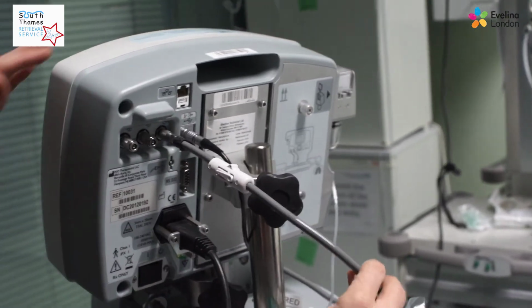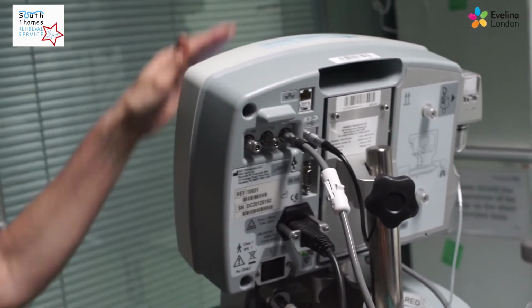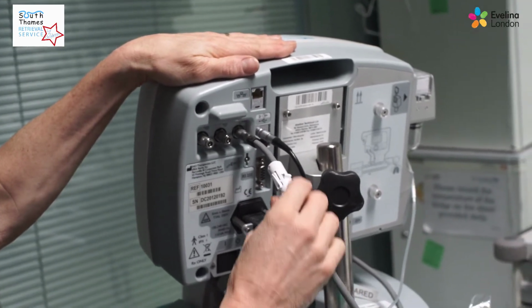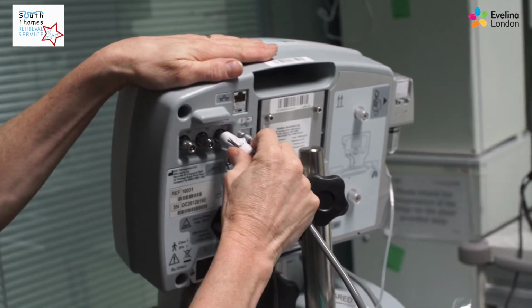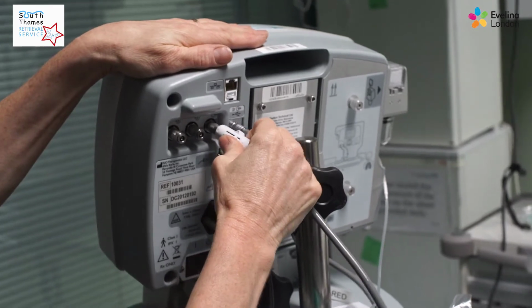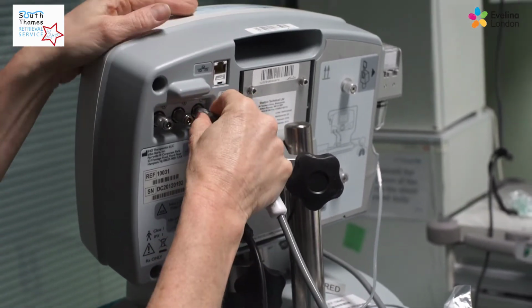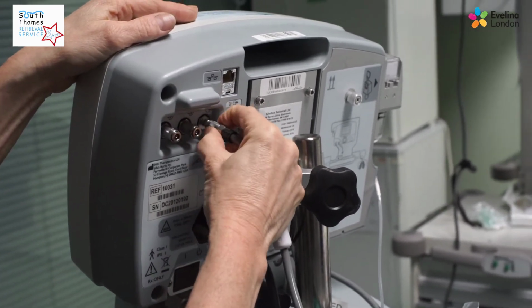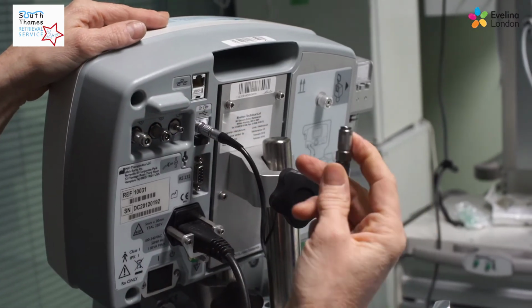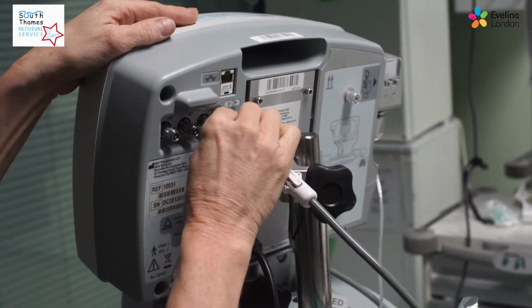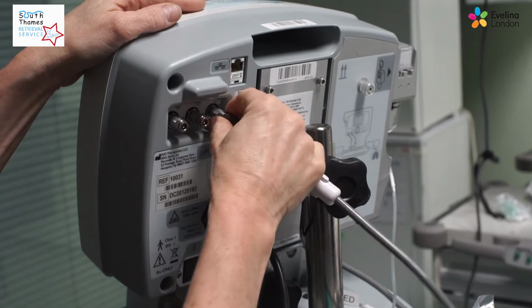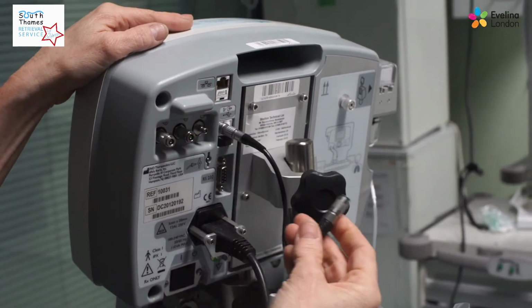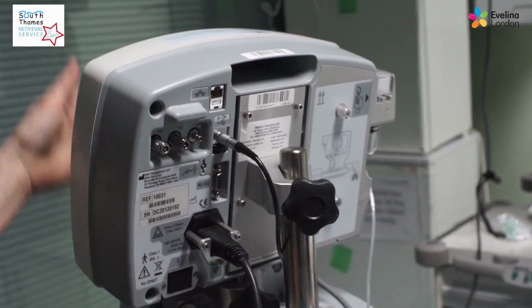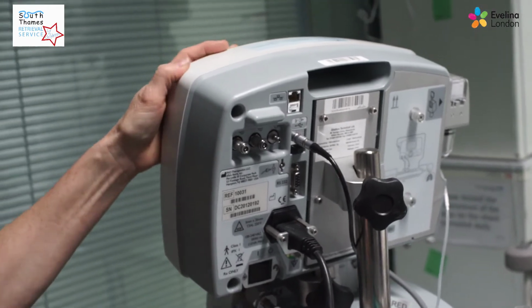Now you need to disconnect the blender from the actual nitric monitor. To do this, there's this white plastic cover over it. You need to move it down, and then with this one you need to pull the collar towards you, towards your fingers, and it will come out. So it's opposite from the other two. And that now means that the monitor and the blender are disconnected.